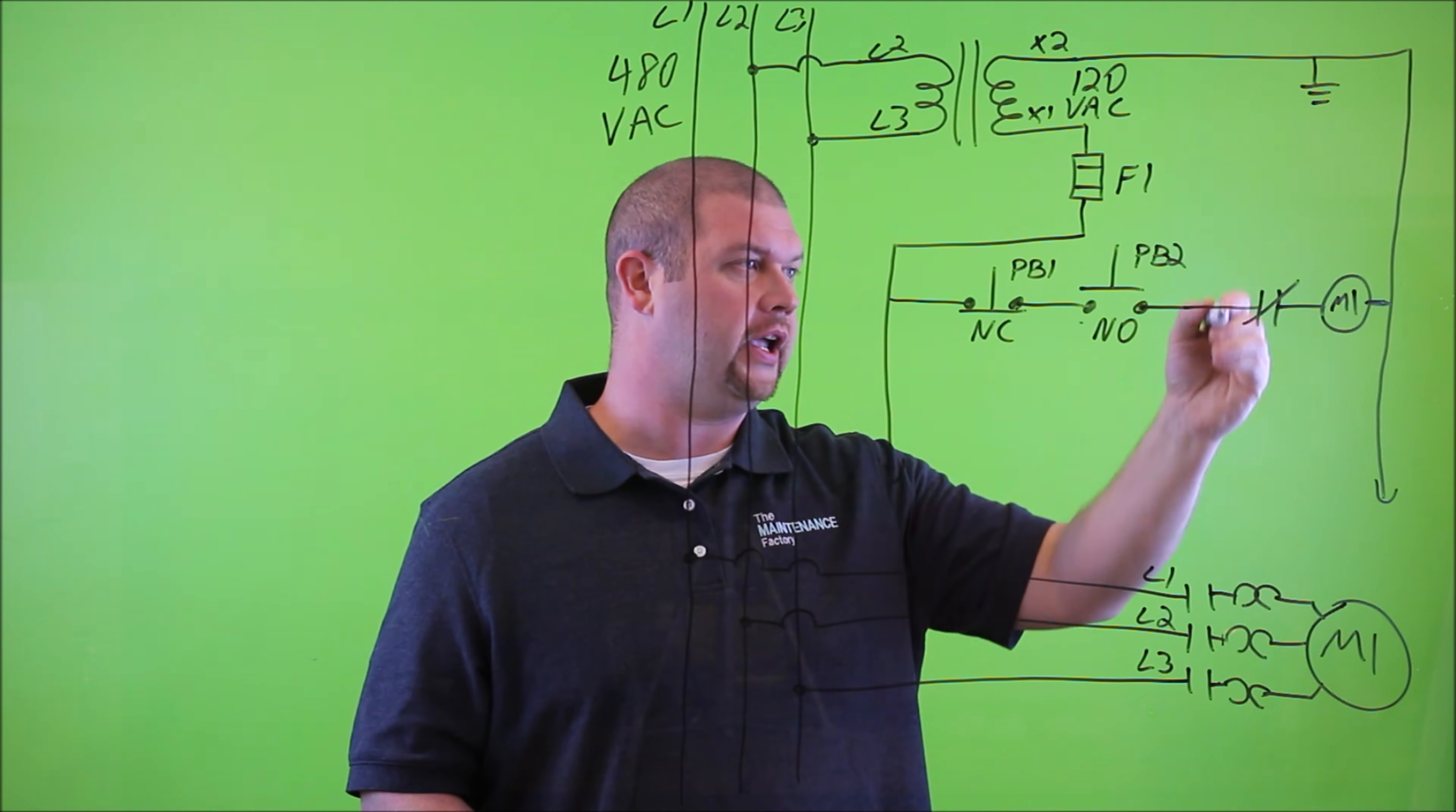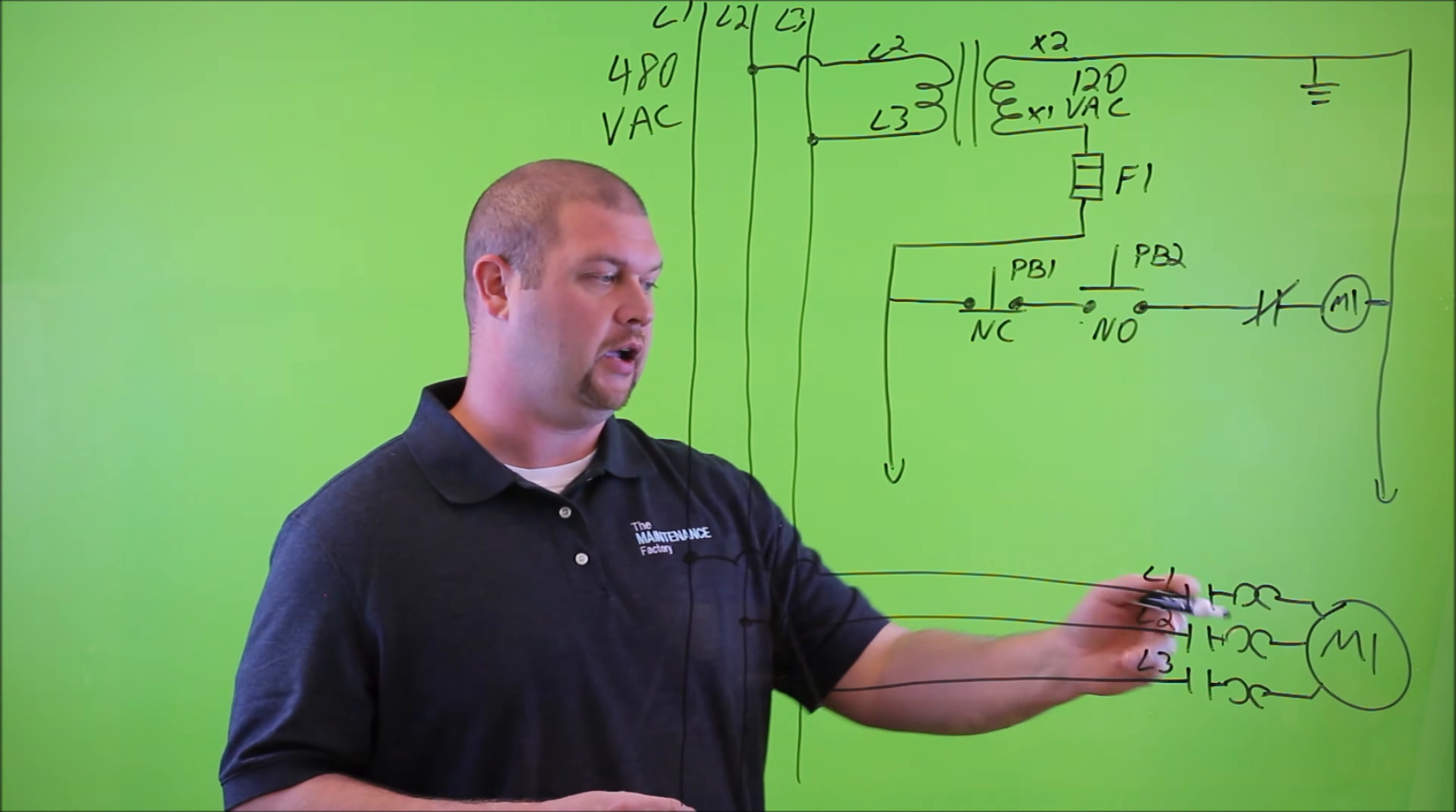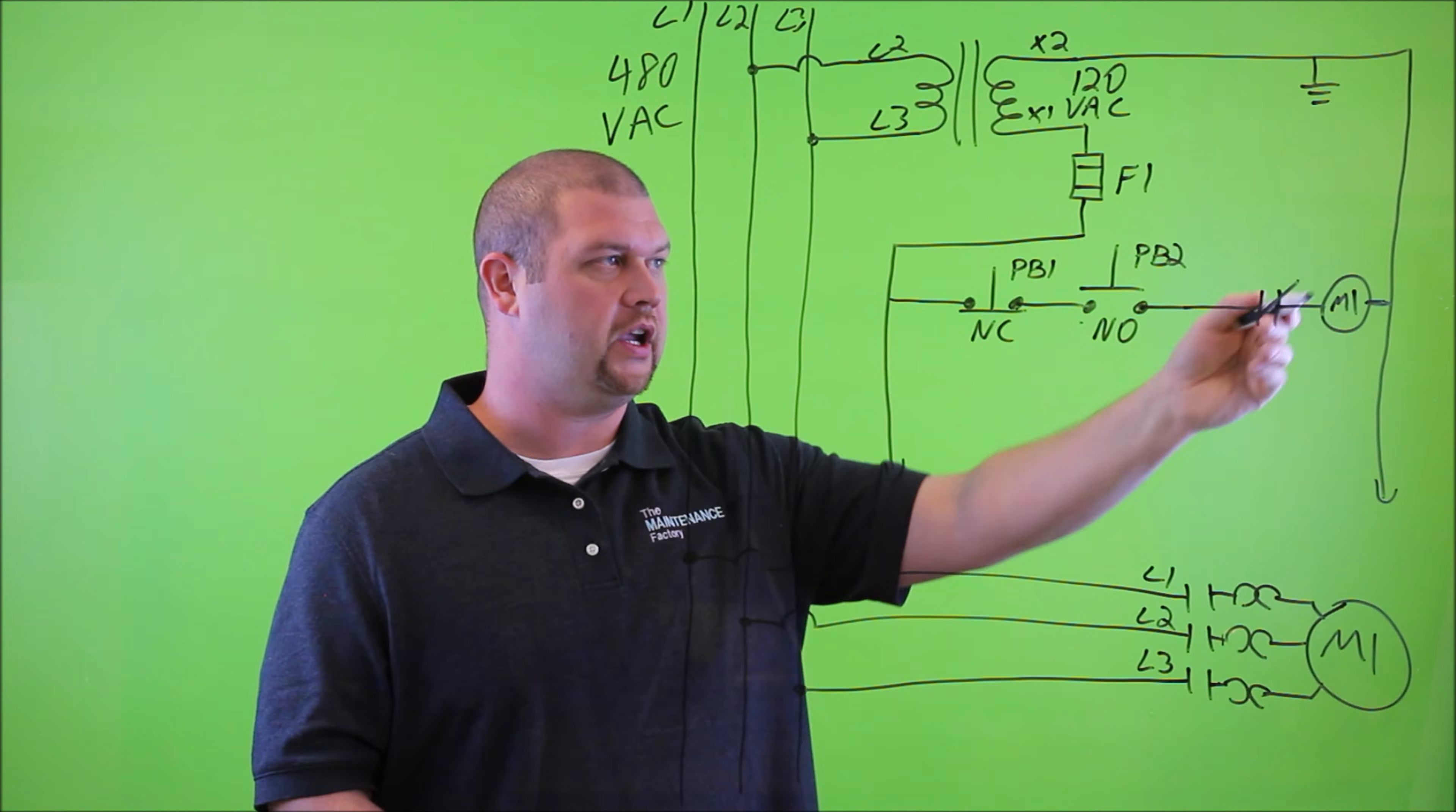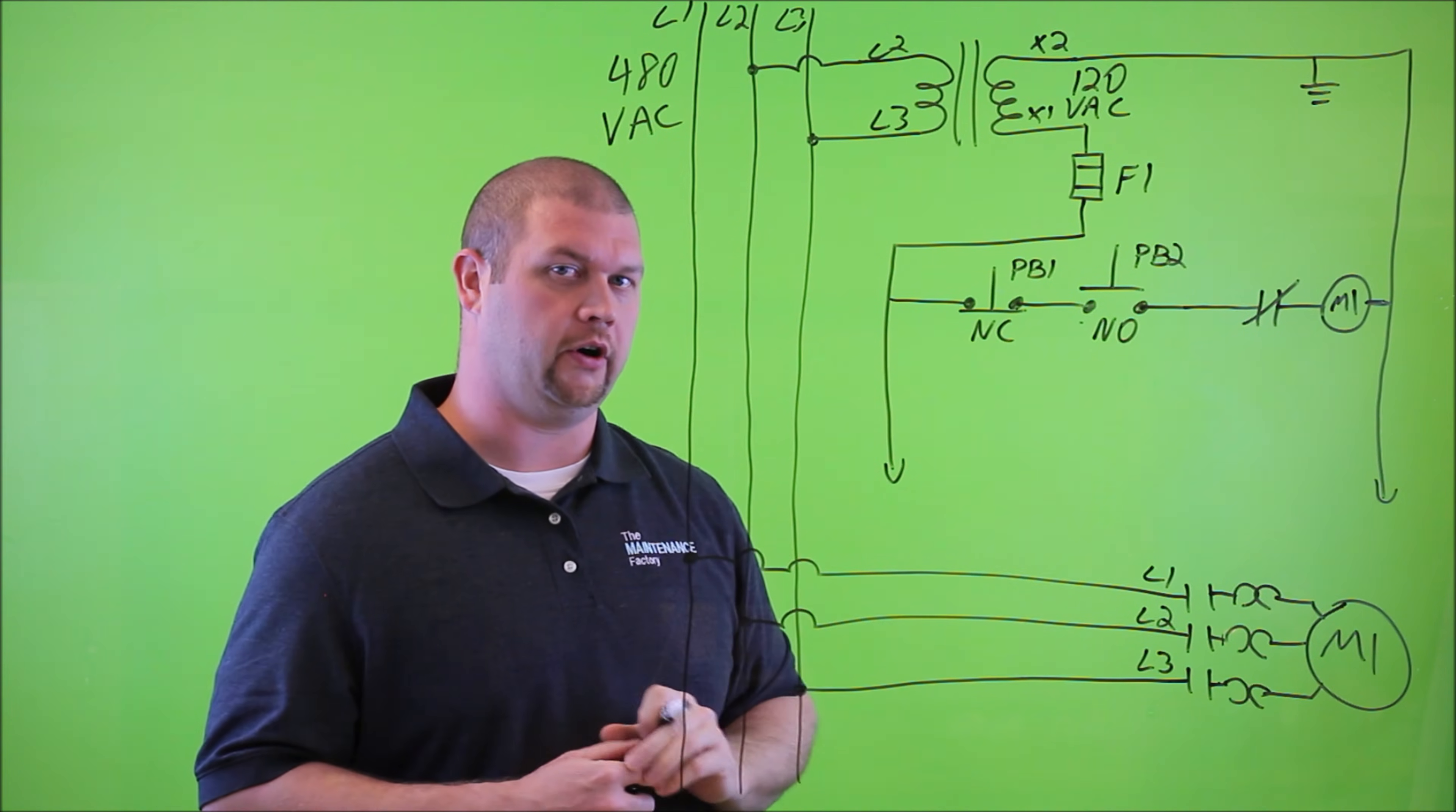Now, this symbol here represents a normally closed set of contacts that will physically exist on this overload right here. So when this overload is in its regular state, it will have a set of contacts on it that are normally closed, not only for each phase of power for the motor, but also an auxiliary contact that we can use to put into this control circuit.